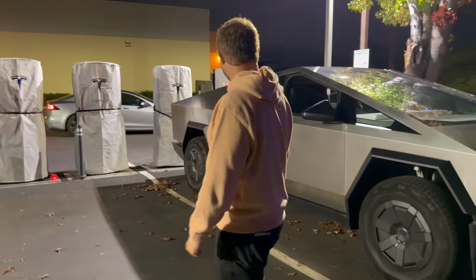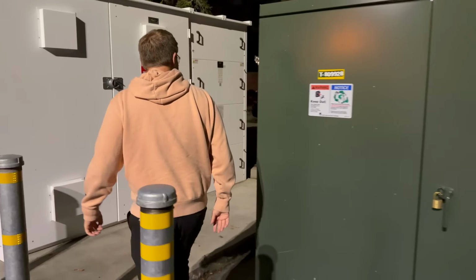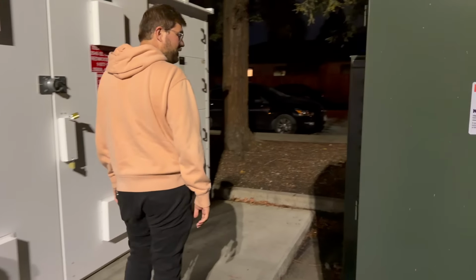100% just hits. All right, let's look at the hardware because this is what's different. We're going to come over here and look at this green thing because this is where the power comes in from the grid. This is a transformer, and its primary voltage isn't so important. I'd be curious what they're doing here, but I don't see it labeled, and I also don't see how many kVA this transformer is capable of. I'm guessing probably a 2000 or 2500 kVA transformer based on the size and the load profile here.